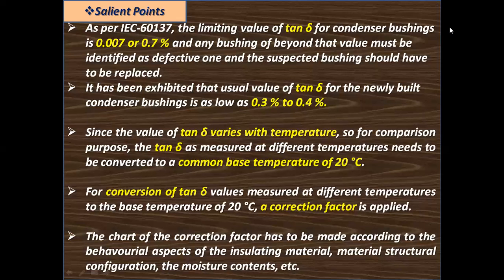Since the value of tan delta varies with temperature, for comparison purposes, the tan delta measured at different temperatures needs to be converted to a common base temperature of 20 degrees centigrade. For this conversion, a correction factor is applied. The chart of the correction factor has to be made according to the behavioral aspects of the insulating material, material structure, the moisture content, etc.